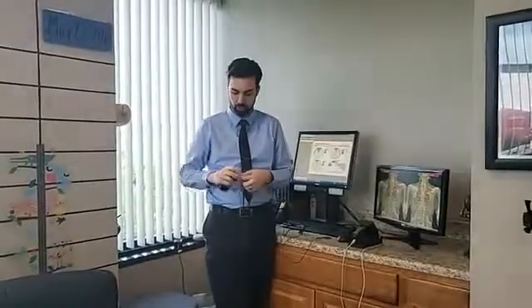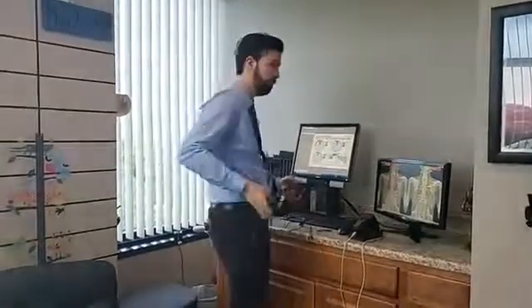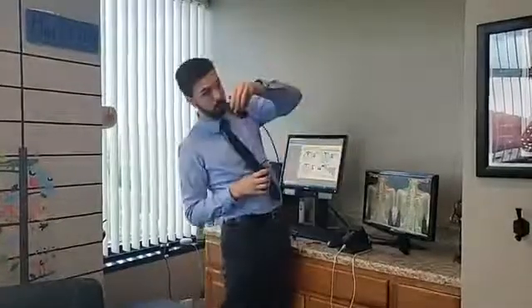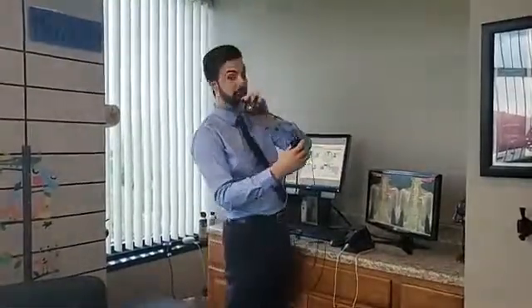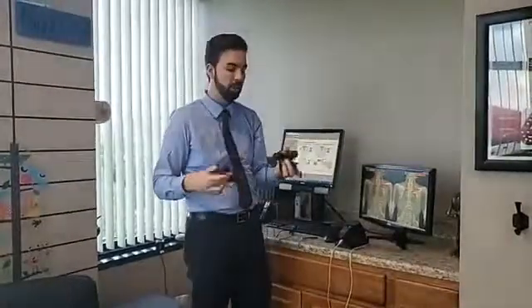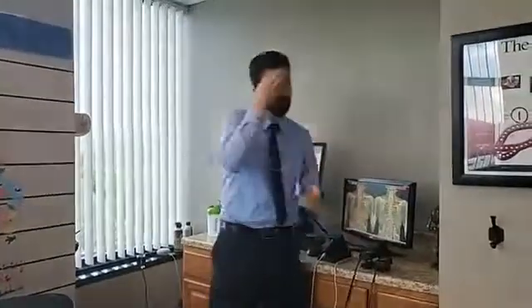With the lumbar spine, you attach the two sensors to each other through a tethered communication cord here, and then one goes down on the pelvis, on the sacrum, right here, and then the other one goes on the bottom of the thoracics. So then you've got the two sensors pointing at each other like this, and then you have them standing and you have them flex forward and lean back and laterally flex and then rotate side to side, and you'll get very reproducible information.